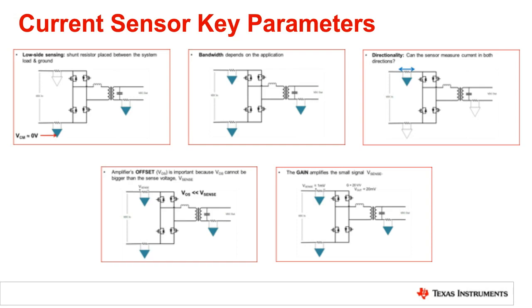Some of these systems will also have inductive kickback, which can actually generate negative common mode. So on the low side sensing, it's important to have a common mode range that can support potential negative voltage, to avoid damaging any of the electronics in the system.